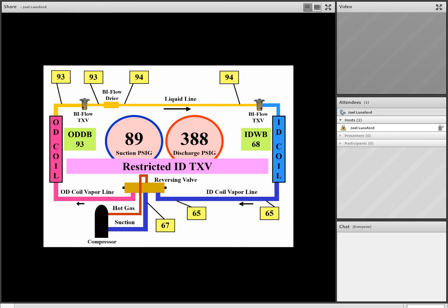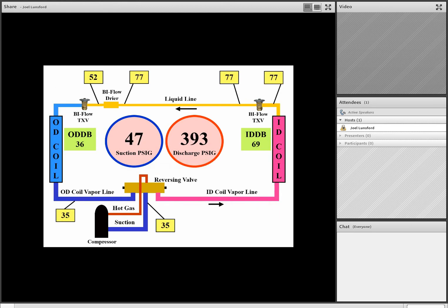Let's switch modes of operation real quick. We see we have a 410A unit in the heating mode of operation. And as we take a look at the temperatures across our components, remember, team, even though it's in the heating mode of operation, the refrigeration cycle still applies. We see we have quite low suction pressure, high discharge pressure. Temperatures across the two cool lines of the reversing valve are normal. The liquid line temperature leaving the warm indoor coil is 77 degrees.